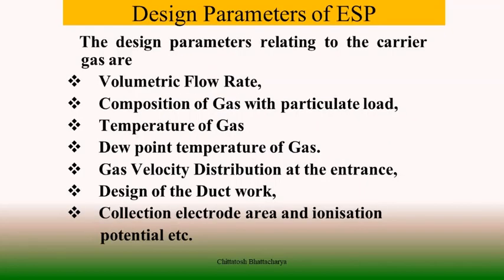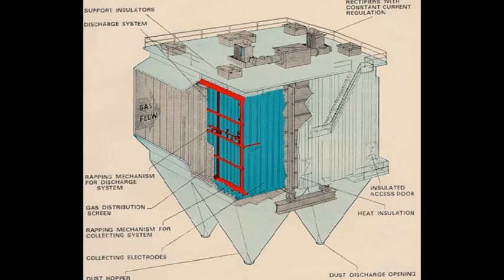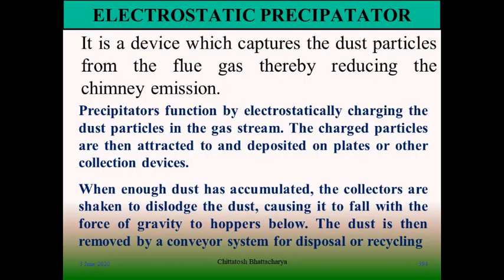The basic design parameters of an ESP in the context of flue gas are: volumetric flow rate of the flue gas, composition of gas with particulate loading, temperature of the gas, dew point temperature of the gas, gas velocity distribution at the entrance of the ESP, design of the ducting in terms of flow, collection electrode areas and their ionization potential. An ESP is a device which captures dust particles from the flue gas and thereby reduces the stack emission by electrostatically charging the dust particles using emitting electrodes inside the gas stream. The charged particles are then attracted to and deposited on collecting electrode plates.